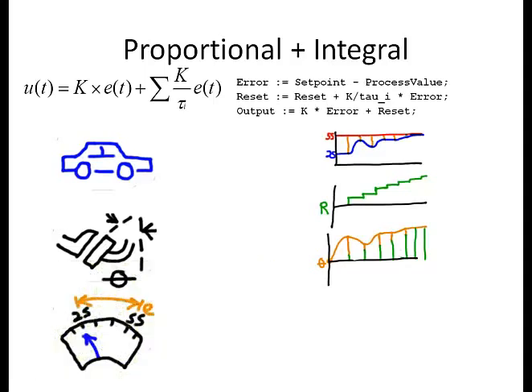You may be wondering why you need proportional at all if the integral component will get you to the set point. Sometimes you don't. If you want a very slow steady rise to a set point change, an integral only controller can be acceptable. But for a controller that you want to quickly get moving in the right direction, the proportional kick for a large error can be very beneficial. Because of this, most controllers in industry are PI controllers.